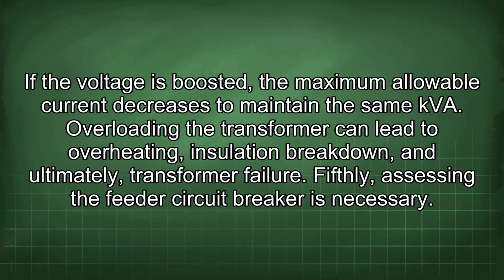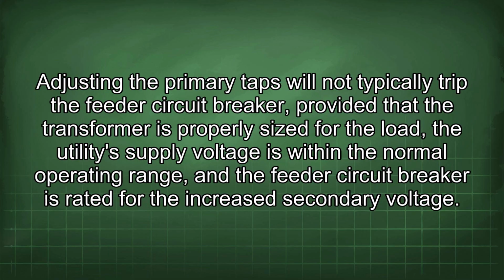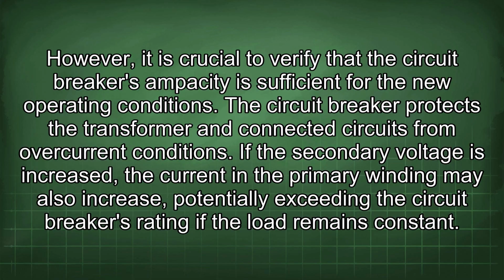Fifthly, assessing the feeder circuit breaker is necessary. Adjusting the primary taps will not typically trip the feeder circuit breaker, provided that the transformer is properly sized for the load, the utility supply voltage is within the normal operating range, and the feeder circuit breaker is rated for the increased secondary voltage. However, it is crucial to verify that the circuit breaker's ampacity is sufficient for the new operating conditions. The circuit breaker protects the transformer and connected circuits from overcurrent conditions.